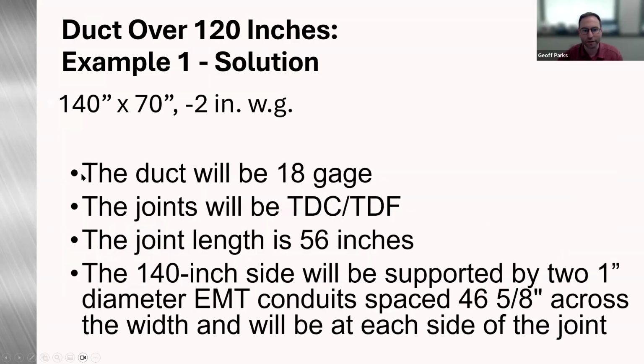So for this one, the duct's going to be 18 gauge. Our joints, we're going to build at a TDC, TDF. Our joint length is 56 inches. For the 140-inch side, the joints are going to be supported by 2 1-inch diameter EMT conduits spaced at 46 5/8 across the width, and they will be on each side of the joint.